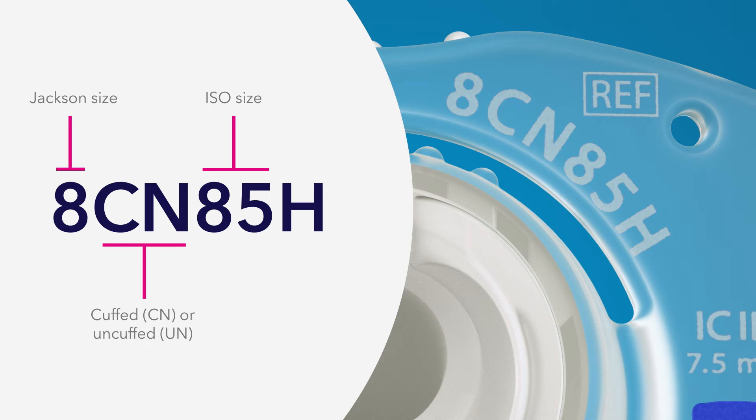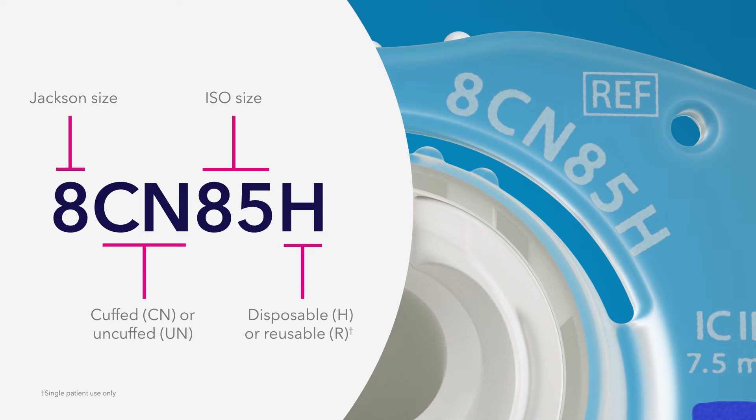The last letter indicates whether the inner cannula is disposable (H) or reusable (R). For a comparable size to the legacy Shiley Tracheostomy tubes, simply reference the first number — that Jackson size — in the product code of the Shiley Flexible tubes.